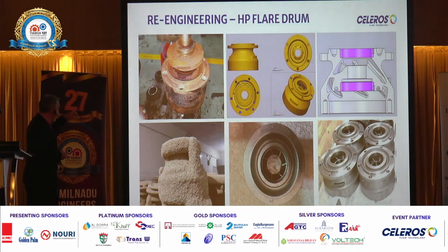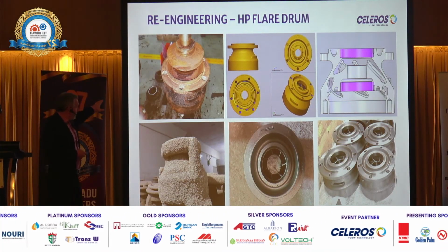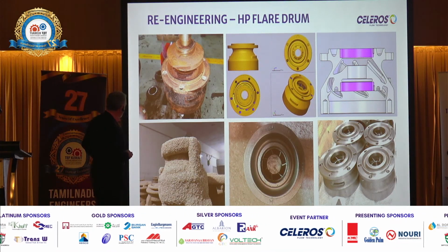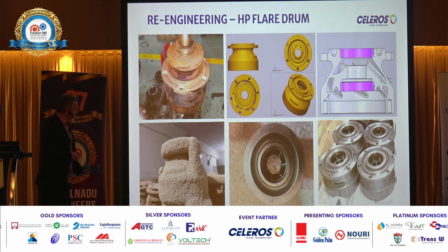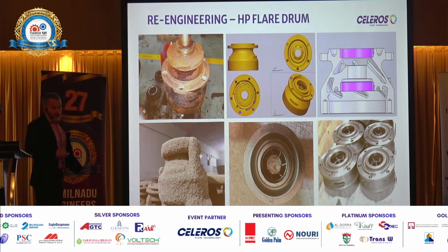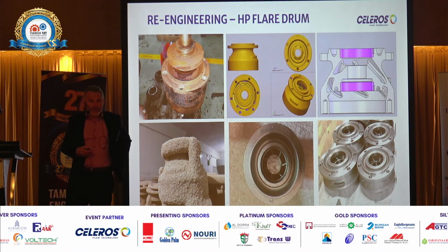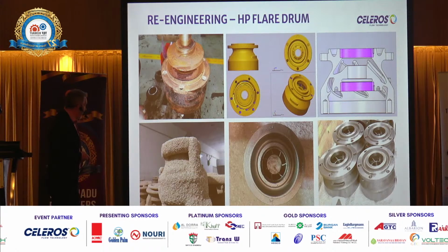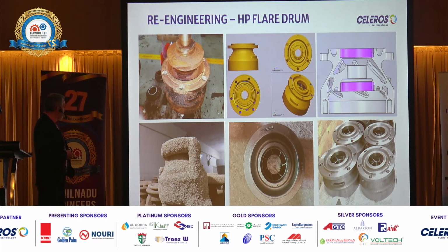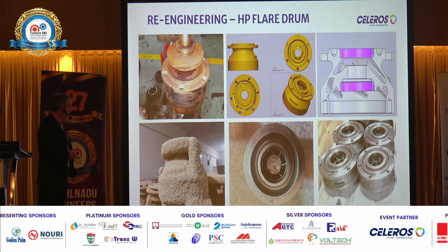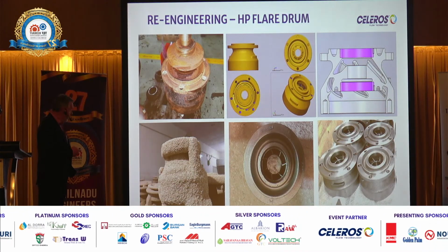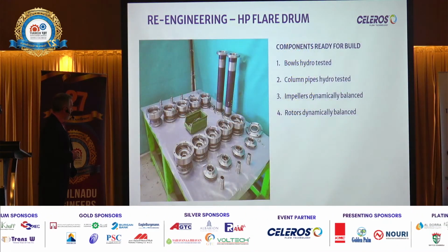So this is one we did. Again, third-party pump. This was actually a Sulzer pump, North Sea. Sulzer, the OEM, told the end user that they needed a new pump, and then they came to us and we said, well, we can actually give you a new pump end. So we scanned all the parts, and this was cheaper than actually buying a pump end from Sulzer.